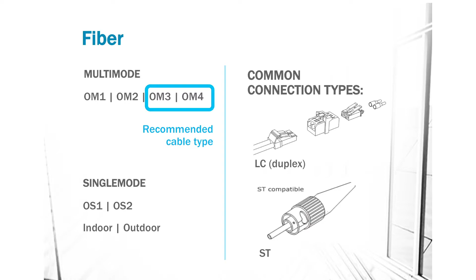That's the only reason I would ever spec OM1, is to match an owner existing. And then here are a couple common connector types. LC is going to be your most common in that duplex format. There are half a dozen others connection types, but again, we're just trying to use fiber to get what we need, and if the client has an IT standard that specifies connector type, great, follow that, and you can just write that into your spec. But if not, LC is fine.